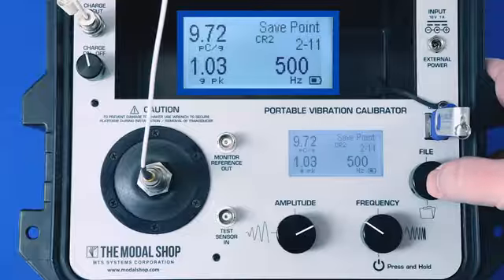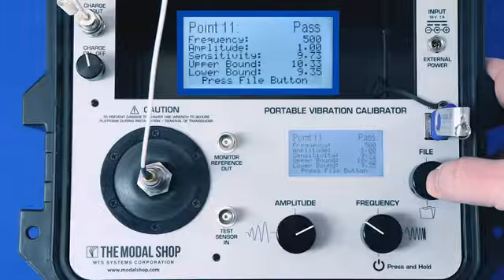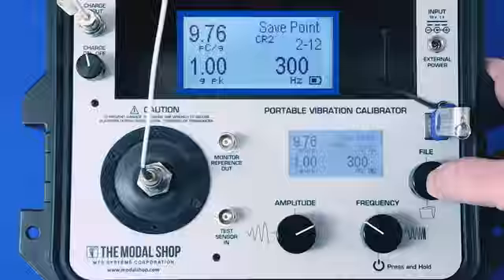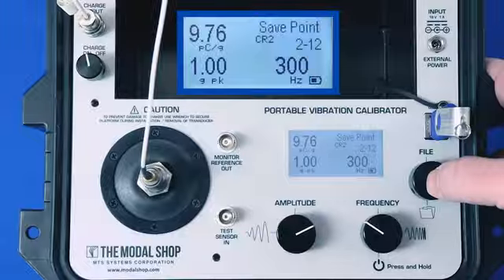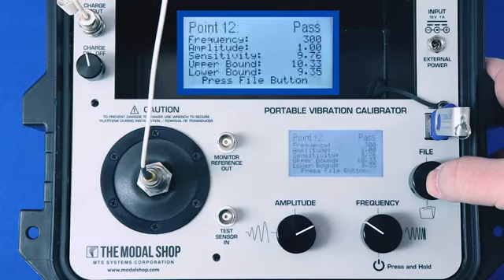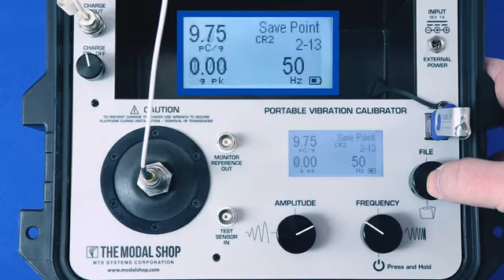And now we're down to 500 Hertz. And again, for each of these test points, plus or minus 5% tolerance is being applied, but some transducers have different specifications, so you can also apply any percentage that you would like, and it also supports asymmetric tolerances as well.